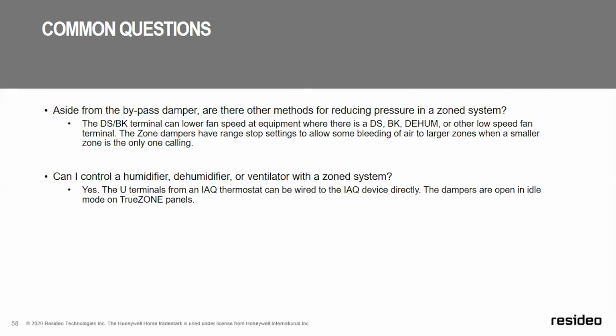And in this situation, I am setting this, going from best case scenario to worst case scenario. And this is where I want to really set my bypass. So just to make sure that we're good in the worst case scenario, I set my smallest zone, and then I want to make sure that my bypass is opening. The bypass damper, the way it's designed, is probably never going to open fully, but you do want to adjust it until it stops opening.